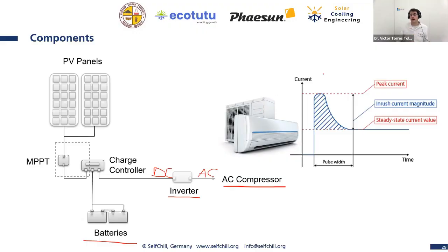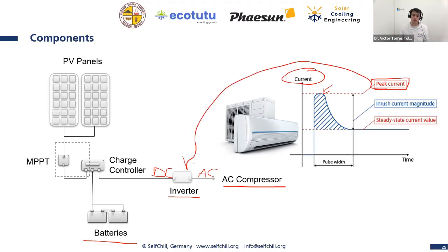The problem is you might have a start current that is much higher than the nominal current, as you can see here. So this is the current, and once you are starting the compressor, you get a peak of current here. And if this peak current is higher than the peak current that your inverter can deal with, then this is not going to work. So always when you are connecting an AC heat pump with an inverter in a solar system, you need to take care that the peak current is not so high that your inverter cannot cope. Otherwise, you will need a bigger inverter, which at the end of the day will cost you money.